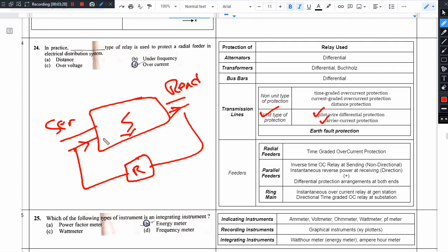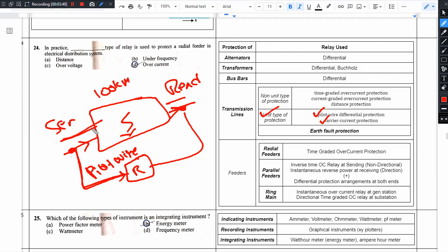Under the unit protection scheme, we have Pilot Wire Differential Protection and Carrier Current Differential Protection. For pilot wire, we compare the sending end and receiving end values — voltage, frequency, current. However, for a 100 km transmission line using ACSR conductor, sending a pilot wire adds significant cost. So we go for Carrier Current Protection instead, where an information signal is superimposed on the AC carrier. This senses sending end and receiving end parameters without a separate wire.